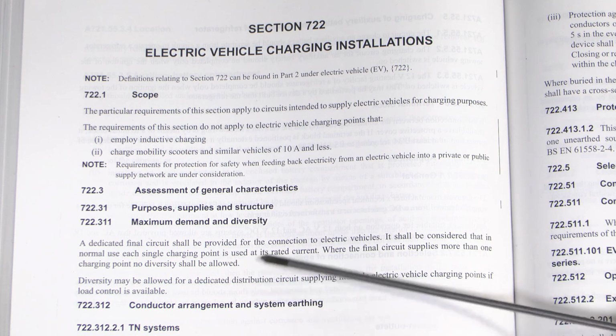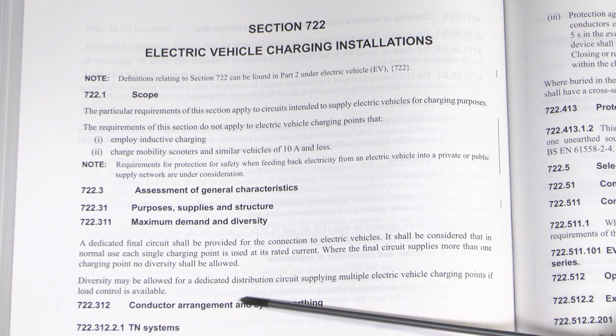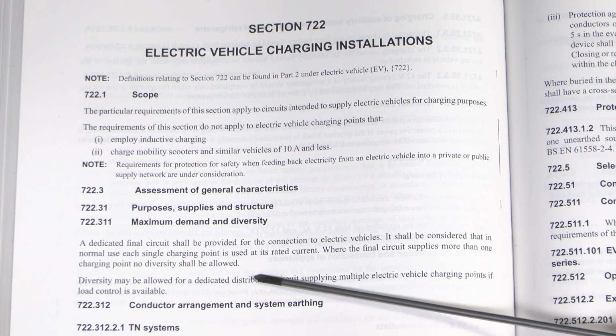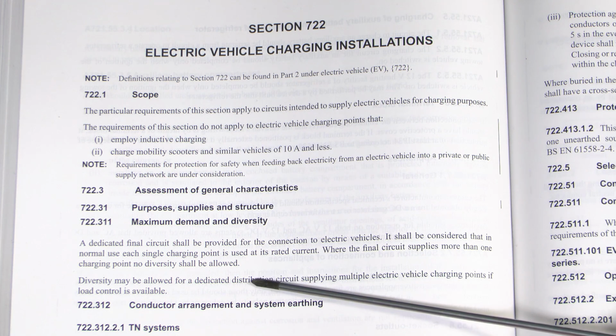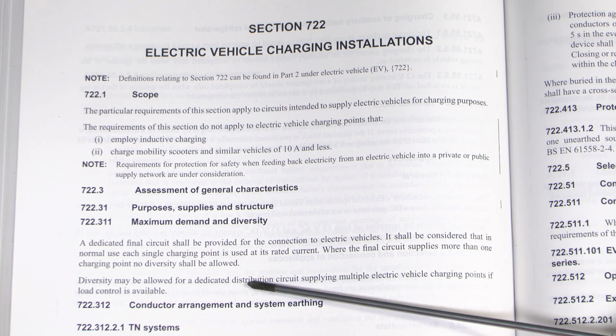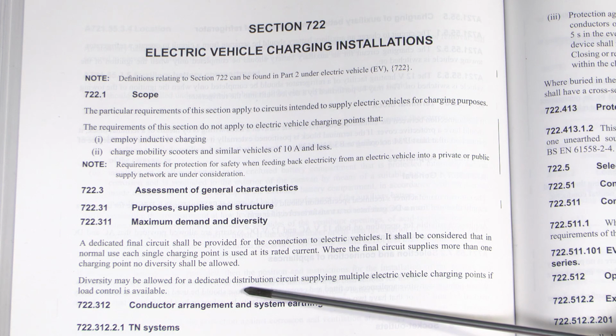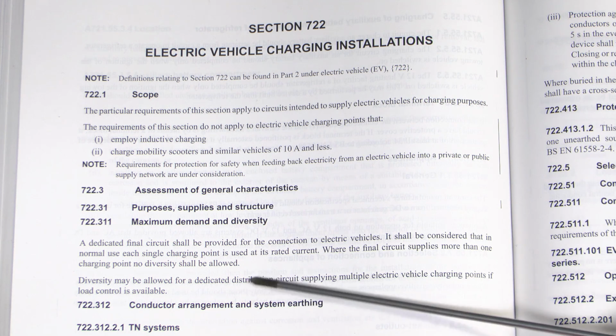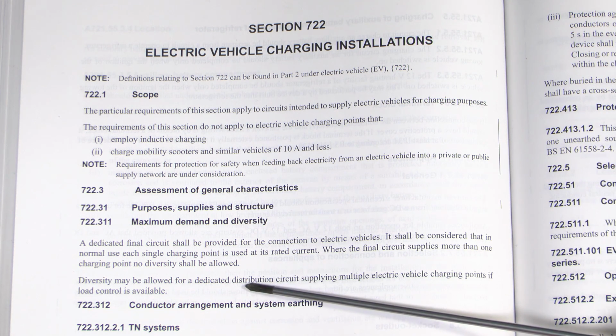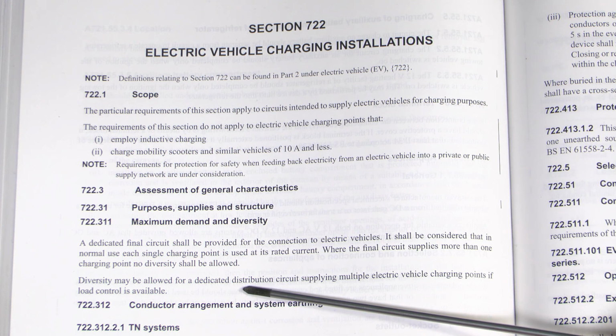And also, unlike things like electric showers, which are typically going to be used for sort of 5-10 minutes, a car charging unit could be in use for many hours continuously. So if it's parked overnight or something, it could be sort of an 8 to 10 hour charging period, and through that 8 to 10 hours it's going to be using the full 30 amps or whatever you've actually provided there.